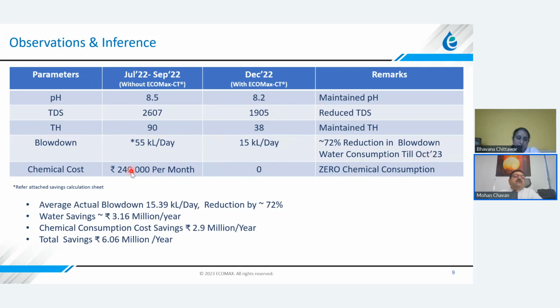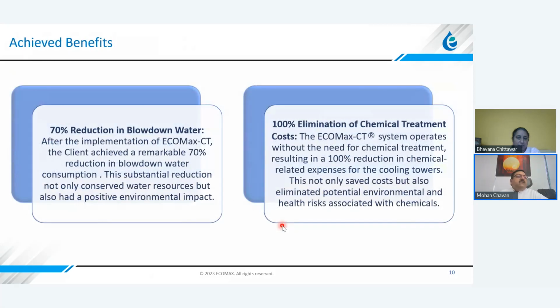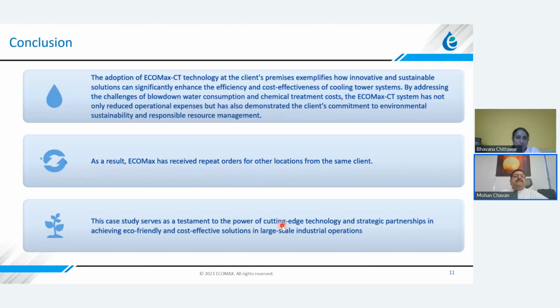And they were consuming almost 2.4 lakhs per month as the chemical cost, and now it's zero. So there's substantial benefit as far as chemical cost reduction and the blowdown reduction are concerned. So overall, they're saving 31.6 lakhs per year. Total savings, for water saving and for chemical consumption, it's 29 lakhs per year, and total savings of almost about 60 lakhs per year. So these were the key benefits from this system for one of the office buildings.